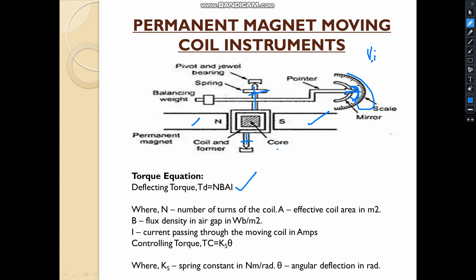The most important equation is the torque equation. Torque is force times distance, where force is BIl and distance is d. Since l times d equals area A, the deflecting torque Td equals N·B·I·A, where A is the effective coil area in square meters, N is the number of turns, B is the flux density in the air gap, and I is the current through the moving coil in amperes.